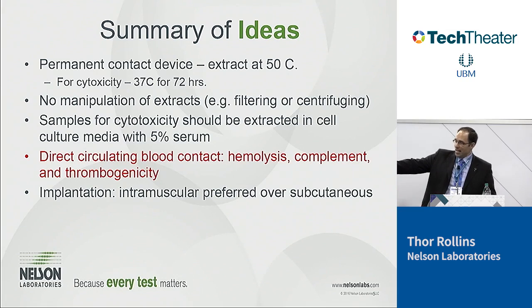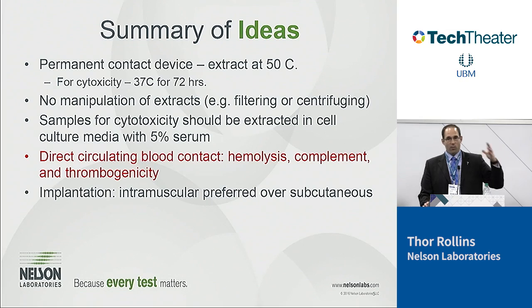But the FDA has come out and said if you have a device that's in contact with the body for more than 72 hours, they want you to extract at 37 degrees for 72 hours. And this is for cytotoxicity, which before we never did. So if you've been running cytotoxicity, you've probably always done a 37-degree extract for 24 hours. If your device is in contact with the body for more than 72 hours, you're going to start having to do a long-term extraction. And what that means for you guys is if you passed cytotox before, and now you're doing a 72-hour extraction instead of 24-hour, it's a more sensitive test, and so you can start to see some failures now with the elevated extraction.